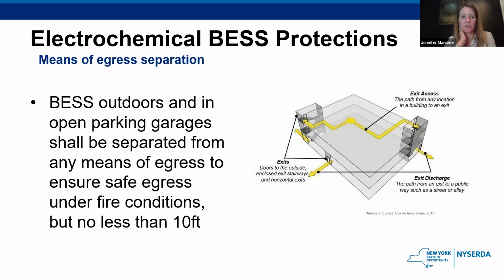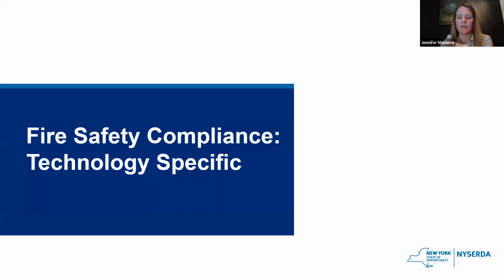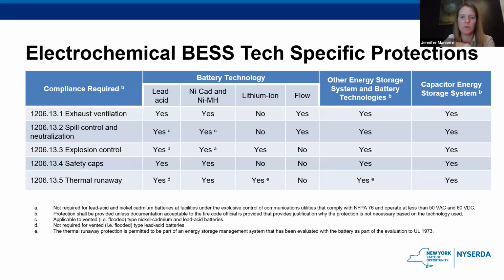There needs to be a means of egress for outdoor systems and in open parking garages. They need to be separated at least by 10 feet. There needs to be a 10-foot path. Okay, so some technology-specific compliance in the code, and these are just excerpts of charts that are in there. I touched on a little bit of this before, but just looking through the different compliance requirements, and we will talk about these over on the left-hand side here. Exhaust ventilation being one, there's spill control and neutralization requirements, explosion control requirements, safety cap requirements, and thermal runaway requirements.